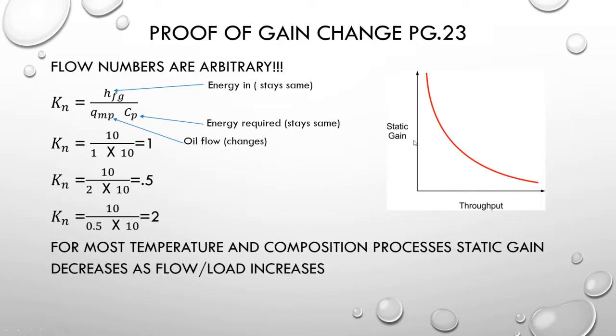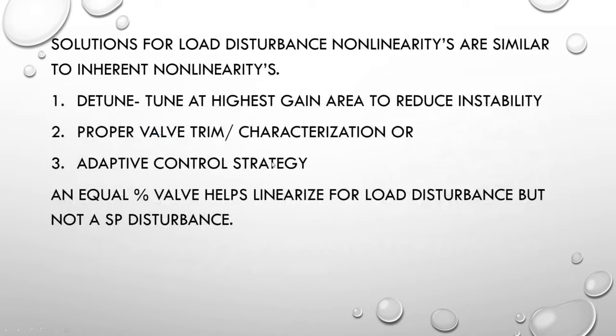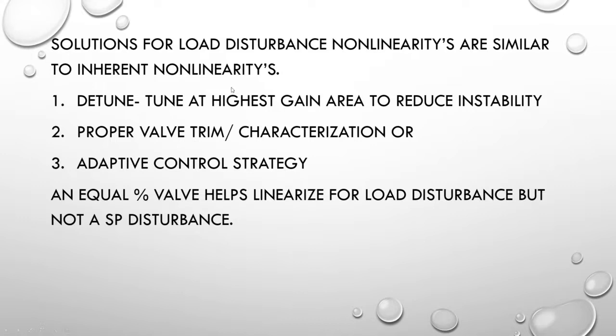So how do we deal with these load disturbances and changing gains? The solutions are similar to what we've looked at for inherent non-linearities from equipment, process, and valve. We have the same options: we can detune — tune at the highest gain area to reduce instability across the board at the expense of possible sluggishness in some areas. Second option is proper valve trim and characterization. Third option is adaptive control strategies. The same strategies can be applied whether we're talking about inherent equipment characteristics or process load disturbance characteristics.